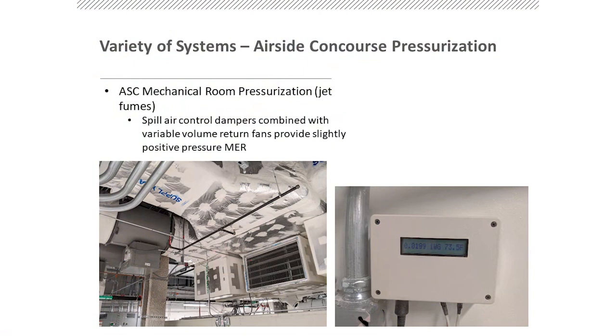In the airside terminal, they were designed in such a way that the mechanical equipment rooms were located with a set of exterior doors that lead straight out to the jetways. So you could have jets idling outside, and these rooms were designed initially as basically where the room serves as an outdoor air, return air mixing plenum. And they were initially designed by the engineer to be slightly negative pressure. And we've had concerns about that. Obviously, we don't want to ingest jet fumes, get them into the MER, because then they end up in the terminal at large.